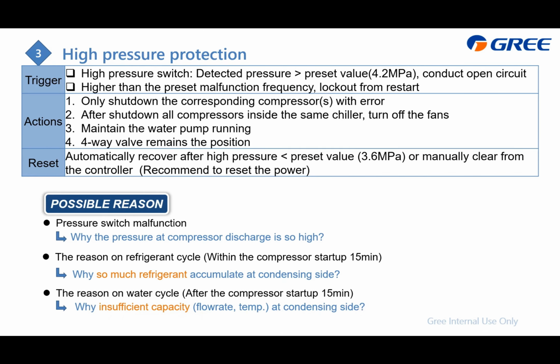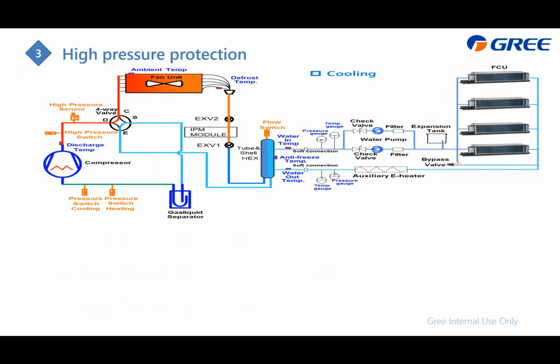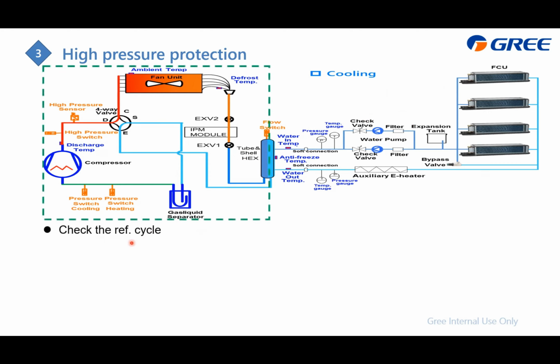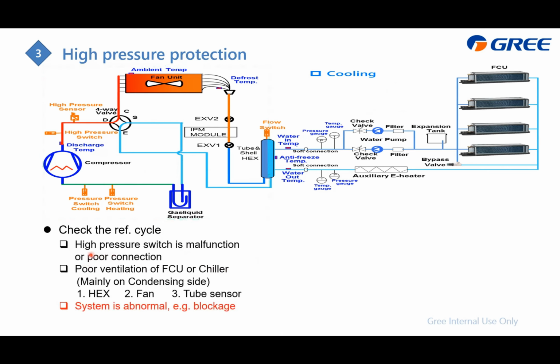And here is, and this is the cooling cycle, for example. On the left side is the refrigerant, right side is the water cycle. And within 15 minutes, check this refrigerant cycle and focus on whether the high pressure, which is this one, is really so high or not, or just maybe it is a malfunction or poorly connected.